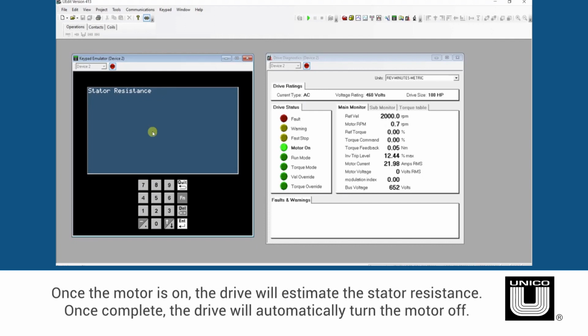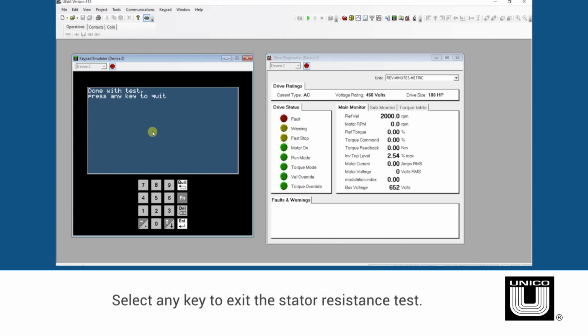Once the motor is on, the drive will estimate the stator resistance. Again, select any key to exit the stator resistance test. Next, select 5 for the phasing test. The ID amps is used for a static alignment, which is run after the phasing test.